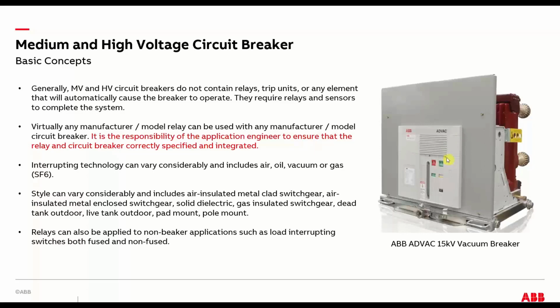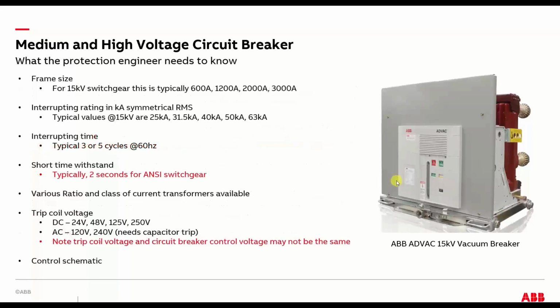But it's got no brain in it. Basically, mostly no sensors, because usually the CTs are part of the switchgear or the assembly it goes into, as this is a draw-out breaker. So it's just the breaker itself, as opposed to low voltage equipment where the breaker's one piece that does it all, plug and play. If you're a protection engineer, the basics you need to know are the frame size.